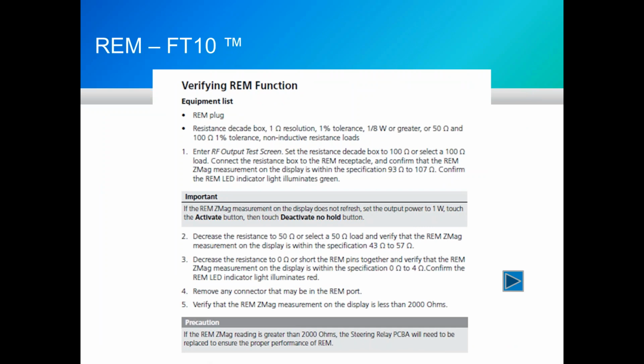So compared to what you have done previously with the Force Triad, the REM test function on the FT10 is significantly different. It is auto-calibrating, so we're not looking for setting a resistance value of 120 ohms and increasing it, looking for that 135 ohm alarm, decreasing down to 5 ohms and looking for the alarm around 4 ohms, and also testing for the 40% increase in resistance and sounding alarm there. In the FT10, we simply dial in 4 different resistances. We'll test at 100 ohms. We will test at 50 ohms. We will test at 0 or short. And we'll also open up the connection to see what the open load resistance would be on the unit itself.